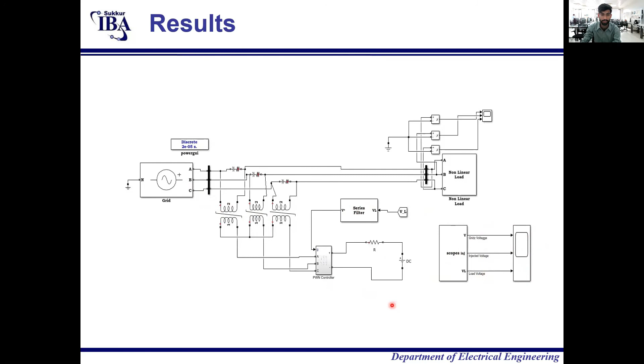The results: this is our harmonics waveform on the load side. But when we use the series active power filter and inject voltages where the sags and swells arise, we can see in the load voltages with the series active power filter that there are no harmonics. And we can see the THD results after connecting the series active power filter. The THD of 16.8% is now 0.77%. The THD is reduced by almost 95 to 97%.